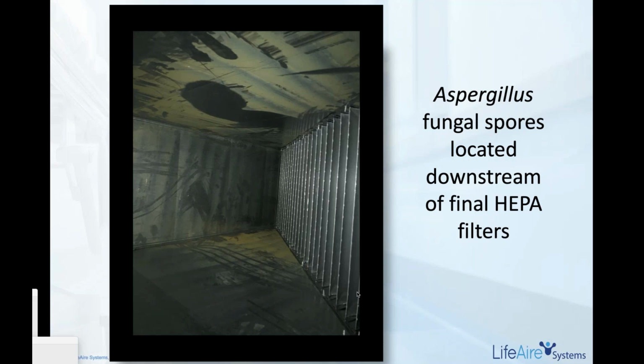This is in the ductwork, and sadly, we see this far too often. This is in the ductwork after the HEPA filter, en route to the space that you're trying to protect. In sampling some of this, these are Aspergillus fungal spores, which are a very common cause of illness. These Aspergillus spores typically are large enough for a HEPA filter to capture. But with a lot of fungal spores, individual cells will shed and pass through or around the HEPA filter. So those working in the space assume that they're protected by the HEPA filtration, yet their ductwork is lined with Aspergillus fungal spores, again, a very common source of illness.